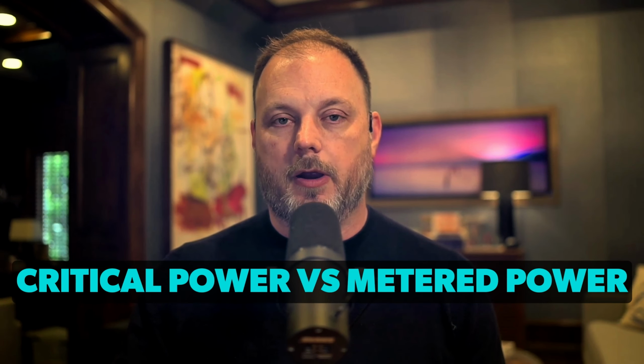This gets harder if you're going into metered power. You have to approach it a bit differently. In the metered power space, you really want to pay attention to: are you getting a panel? How many breaker positions are available to you in the panel? How do those breaker positions in that panel actually equate to circuits in the floor space? And what's that comparison against your density if you were just to take critical circuits—critical power versus metered power?